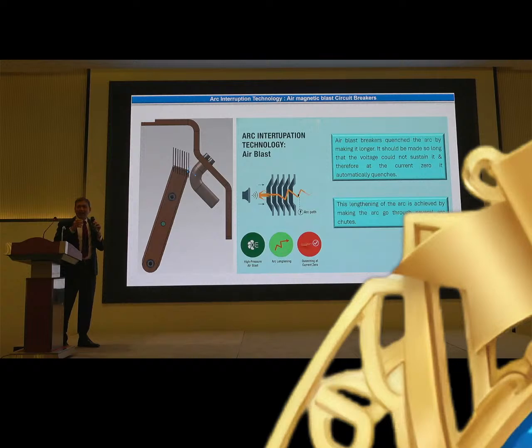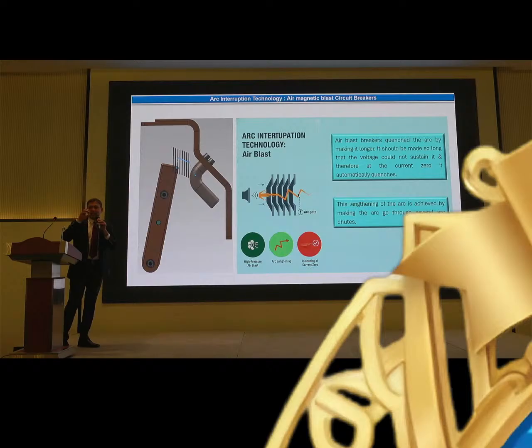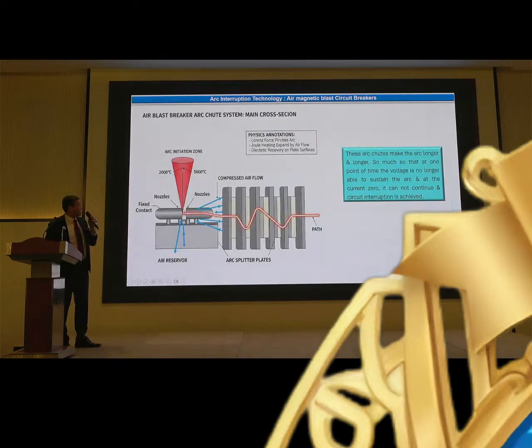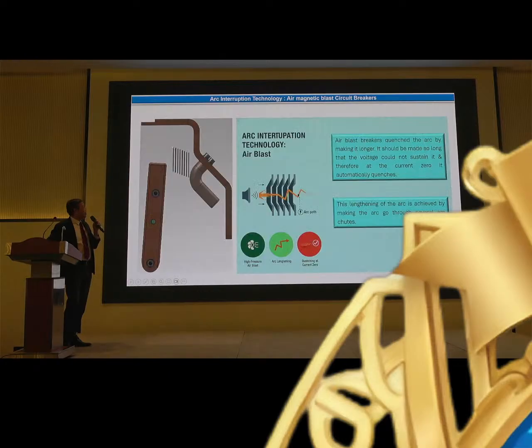So my job is to make the arc longer in older circuit breakers. This is the first technology. How do we make it long? How do you blow out a candle? By blowing on the arc, you make it longer and it goes off. In the breaker, I use compressed air and blow the arc over many arc separators. These are called arc separators, arc chutes. So the arc clears. So this was the air circuit breaker.